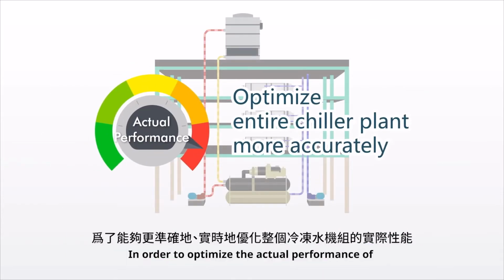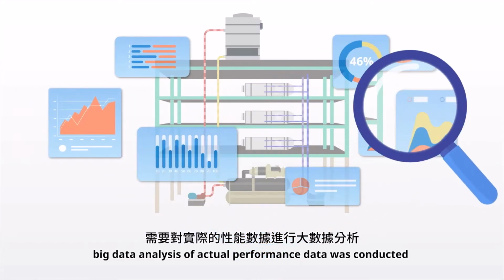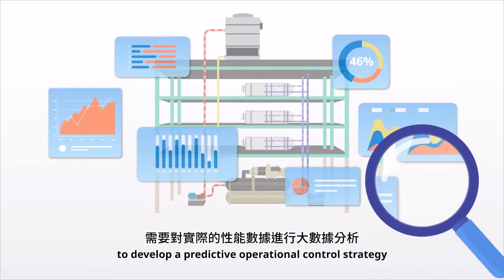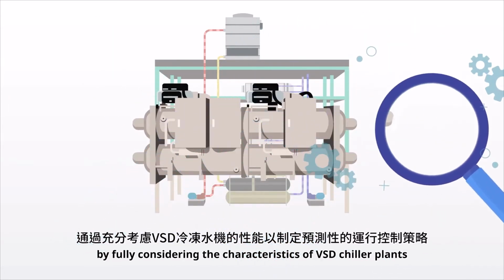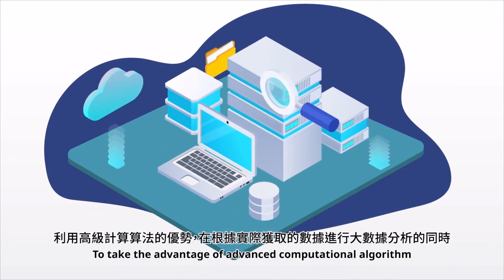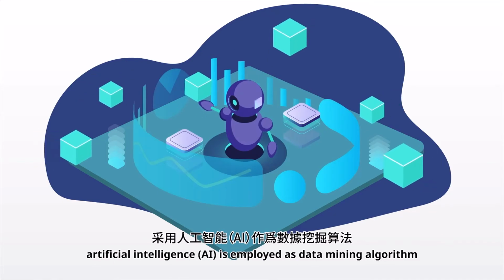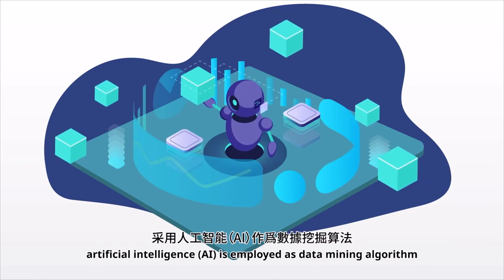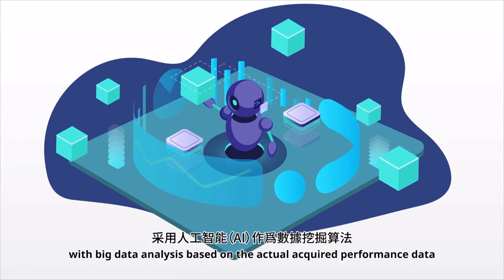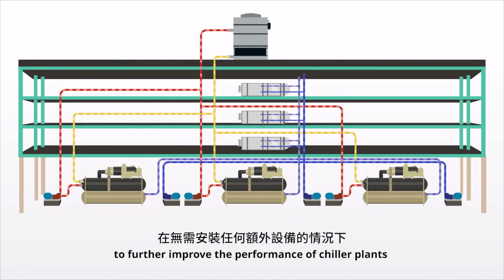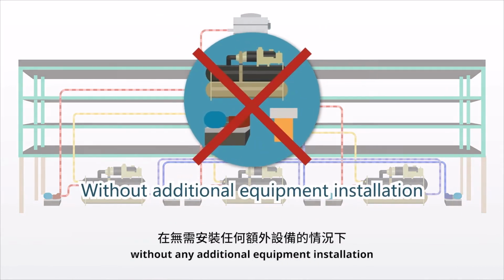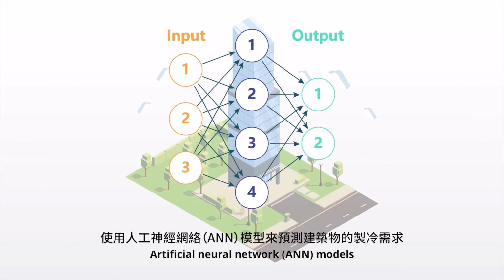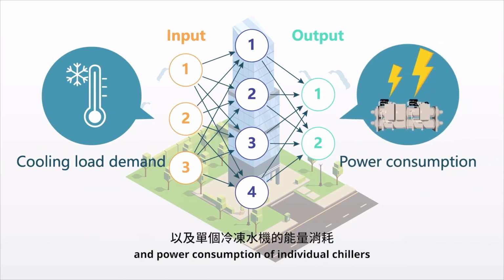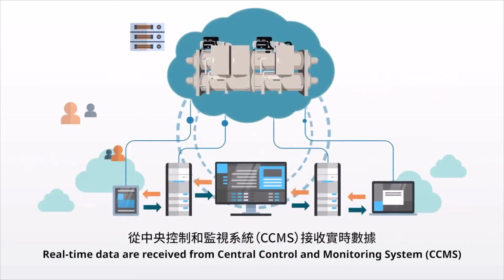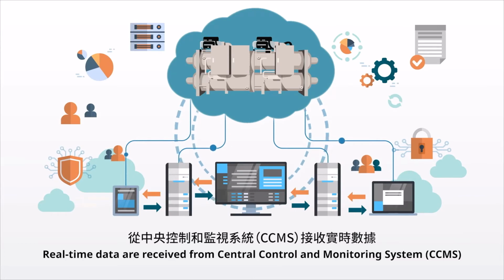In order to optimize the actual performance of the entire chiller plant more accurately in real time, big data analysis of actual performance data was conducted to develop a predictive operational control strategy by fully considering the characteristics of VSD chiller plants. To take advantage of advanced computational algorithms, artificial intelligence (AI) is employed as a data mining algorithm, with big data analysis based on the actual acquired performance data to further improve the performance of chiller plants without any additional equipment installation. Artificial neural network (ANN) models are adopted to predict the building cooling load demand and power consumption of individual chillers. Real-time data are received from the Central Control and Monitoring System (CCMS).